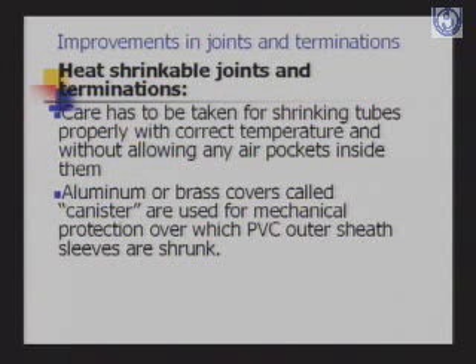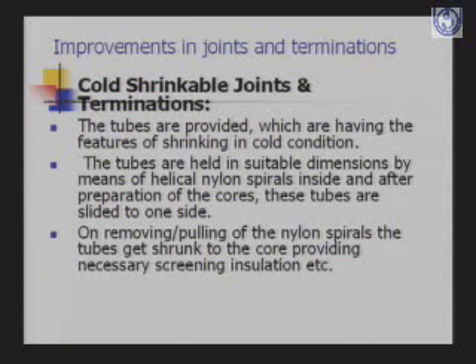Care has to be taken for shrinking tubes properly with correct temperature and without allowing any air pockets inside them. Aluminium or brass covers called canister are often used for mechanical protection, over which PVC outer sheath sleeves are shrunk. Then we also have the cold shrinkable joints and terminations, where you do not want to heat with a blow lamp. The tubes are provided which have the feature of shrinking in cold condition.